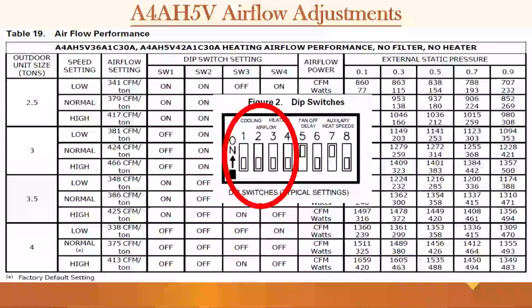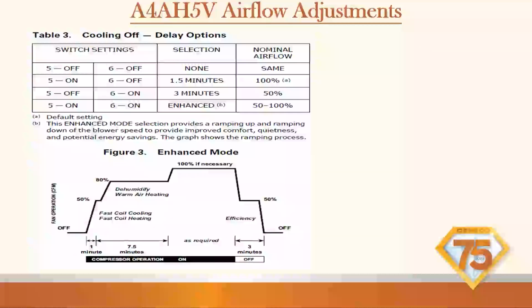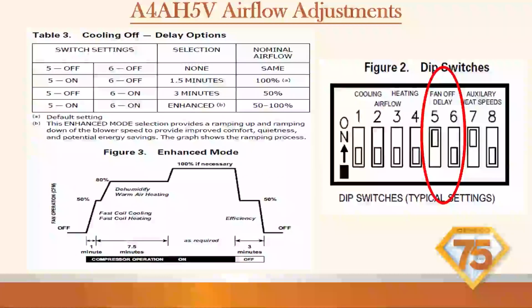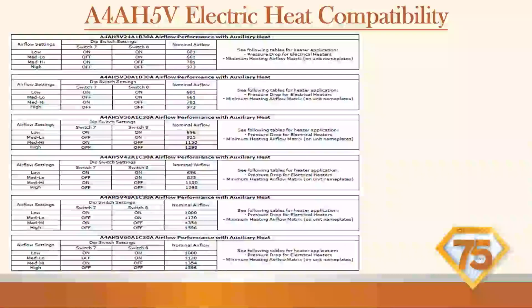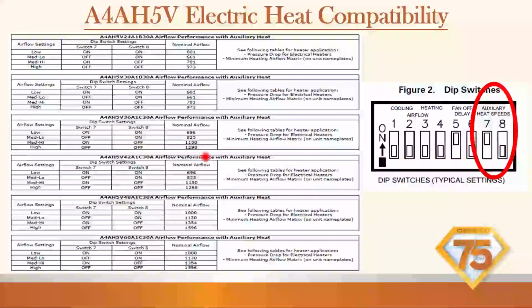More airflow adjustments. Again, turn the power cycle down. So turn off the unit, set your dip switches, re-energize. Won't spend too much time on that. Give tech services a call if you guys would like to discuss that a little bit more, or anything in here. You guys can always call in because I know I'm moving pretty quick through this. There's your auxiliary heat speeds. Again, it'll go through. Here's our 3-ton, 2.5, 2-ton, 3.5, 4-ton. These are the airflow settings. So you will have to adjust that per heat strip that you have in there.